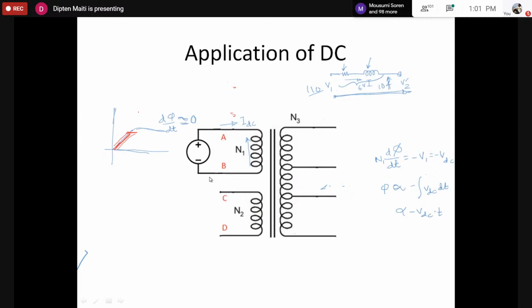However, in the lab, if you apply rated DC voltage without restriction, say 110 volt DC, that may damage the transformer. If you apply a fuse for safety, that makes the transformer safe and can actually save it.